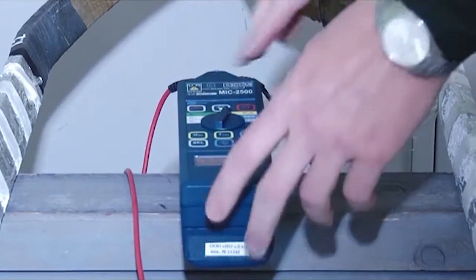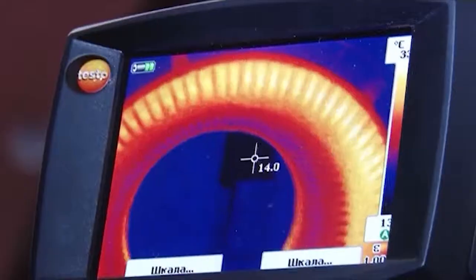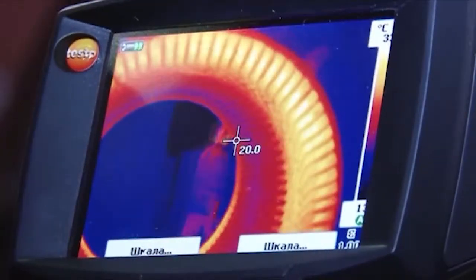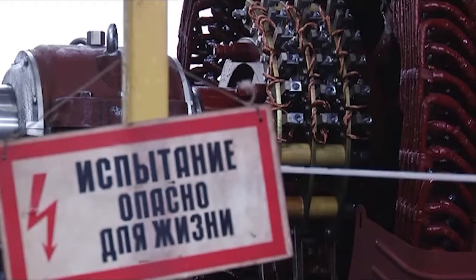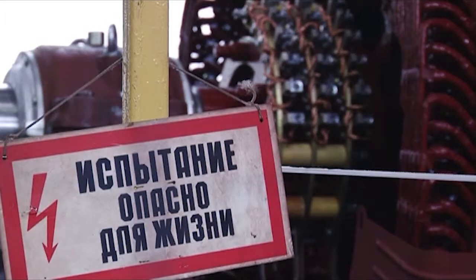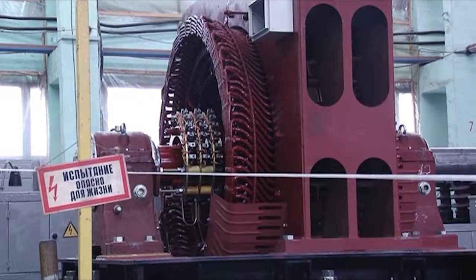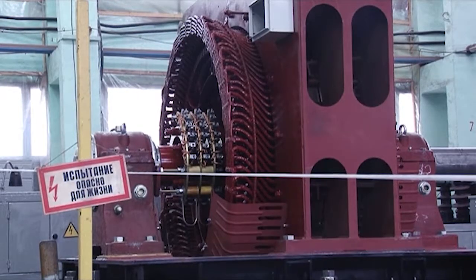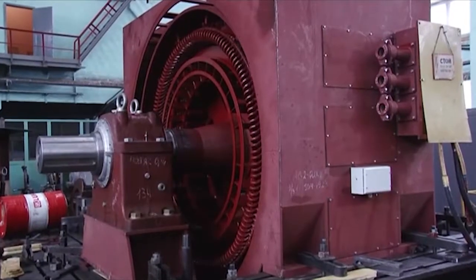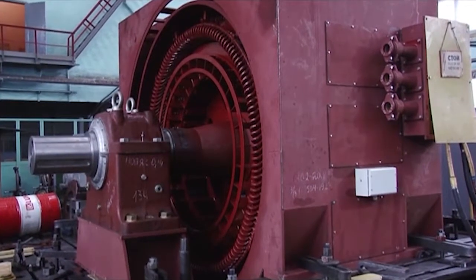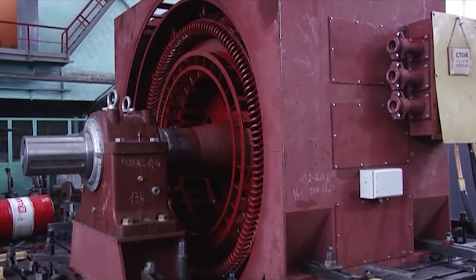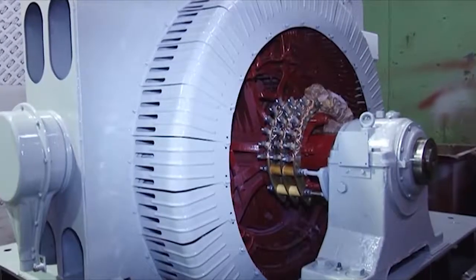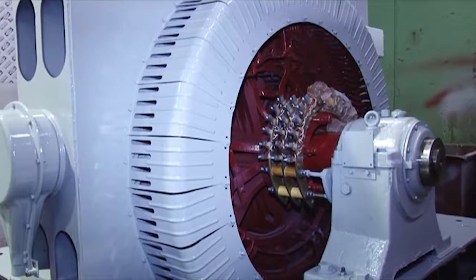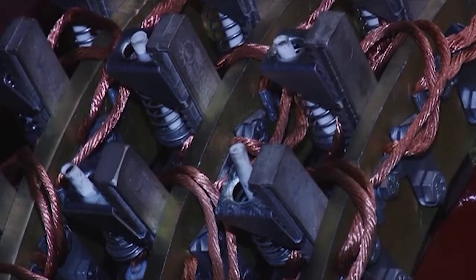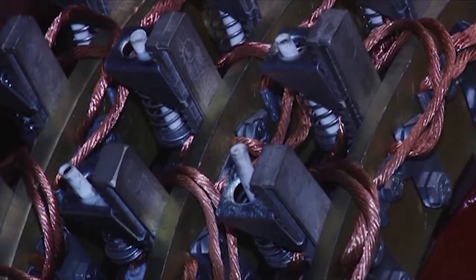The stator winding connection circuit is subject to thermo-visual control. The motor is then subject to various tests on a test rig after assembly has finished. Noise level, vibration severity and air gap efficiency, power factor and slip ratio, initial starting torque, as well as other parameters are measured during the tests. Safety of the motor operations is also confirmed during these tests.